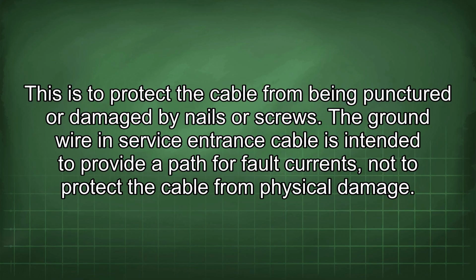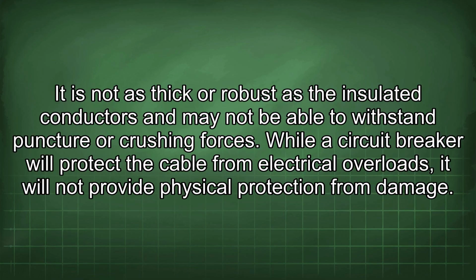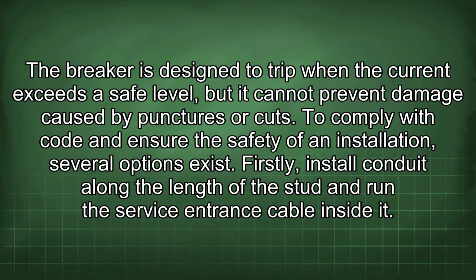The ground wire in service entrance cable is intended to provide a path for fault currents, not to protect the cable from physical damage. It is not as thick or robust as the insulated conductors and may not be able to withstand puncture or crushing forces. While a circuit breaker will protect the cable from electrical overloads, it will not provide physical protection from damage. The breaker is designed to trip when the current exceeds a safe level, but it cannot prevent damage caused by punctures or cuts. To comply with code and ensure the safety of an installation, several options exist.